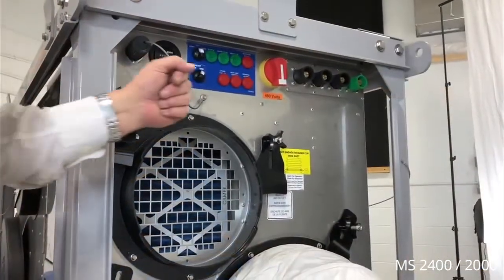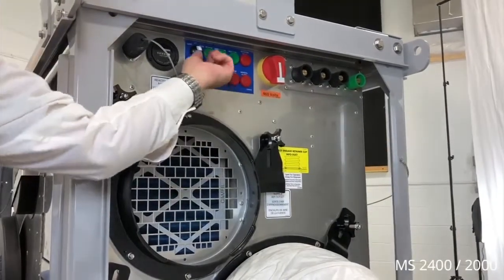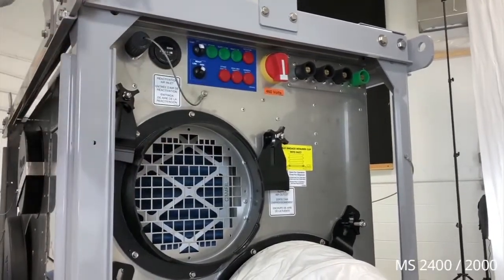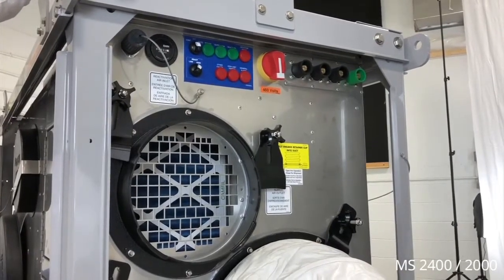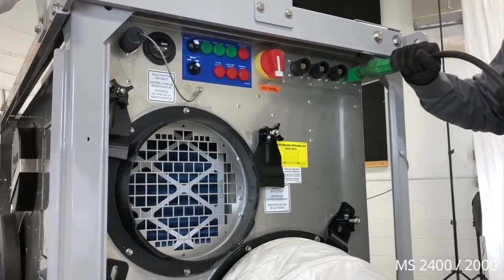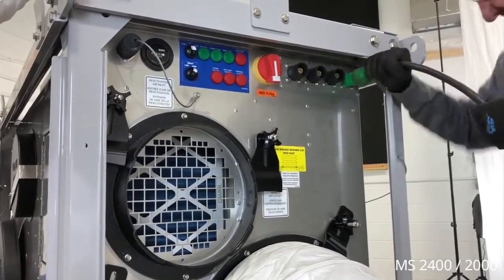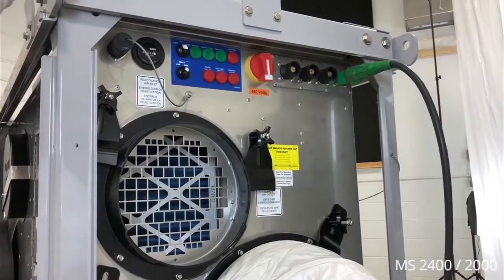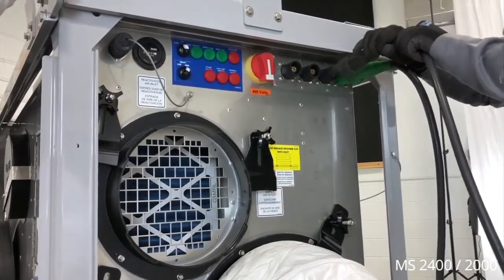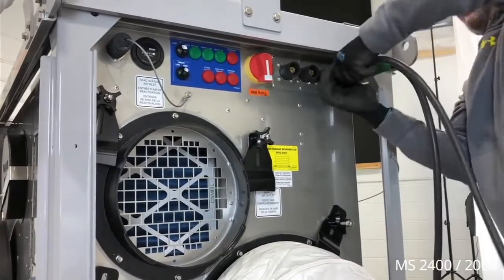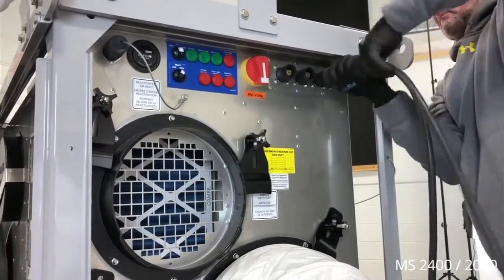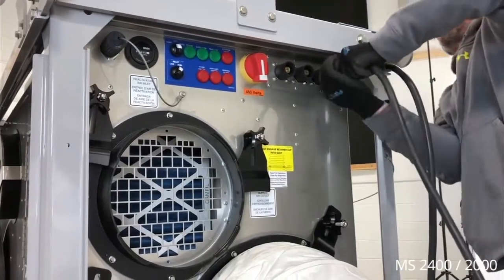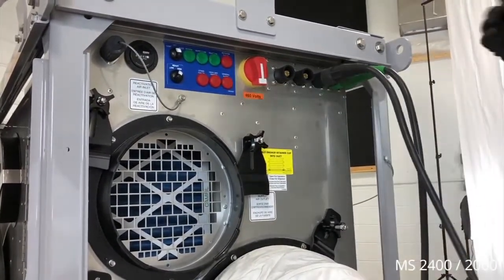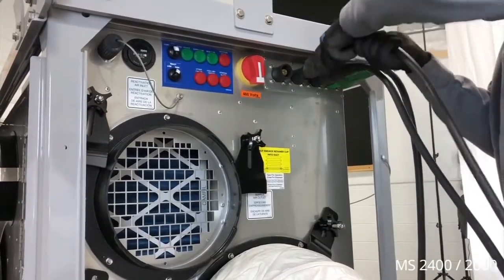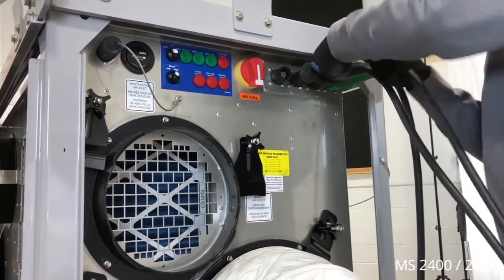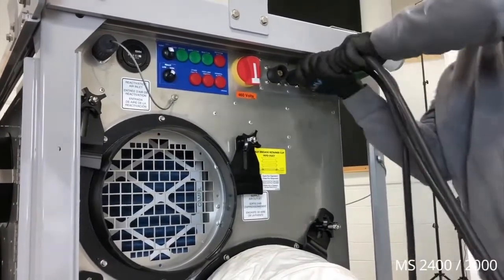With the generator off and the disconnect off and the selector switch off, we can now connect main power to the dehumidifier, starting with the ground wire. Power can be 460 volts to 480 volts, 3-phase, 60 cycles. Make sure and double verify all of the connections are tight as you twist the connectors. These are 400 amp cam lock connectors, considered the large connector.